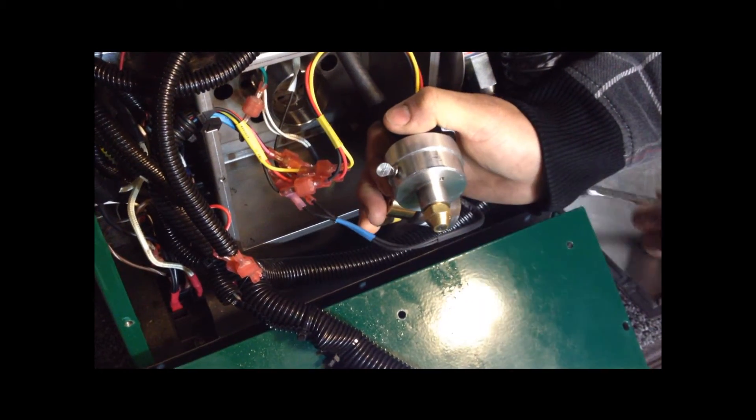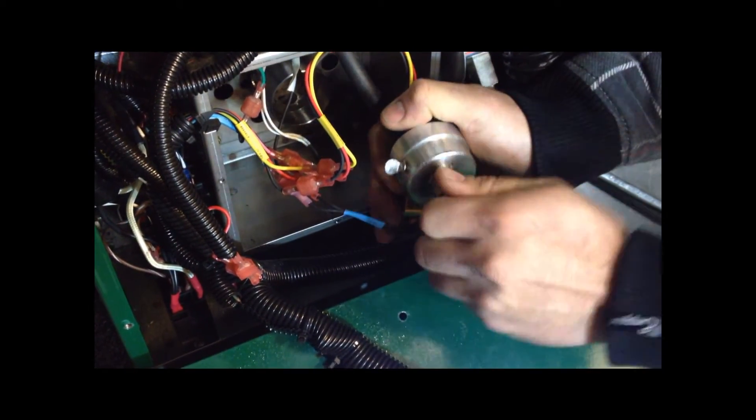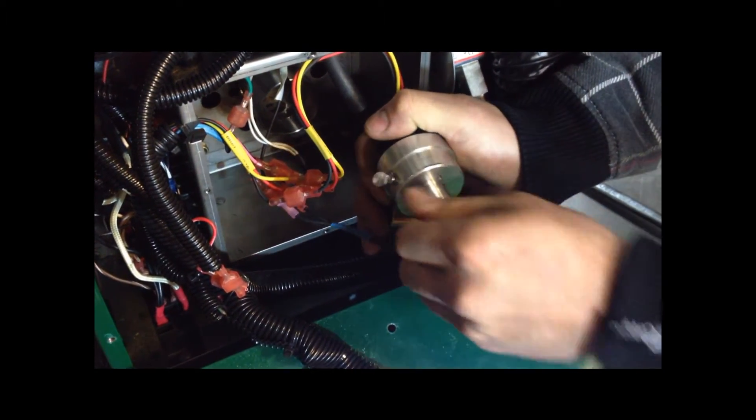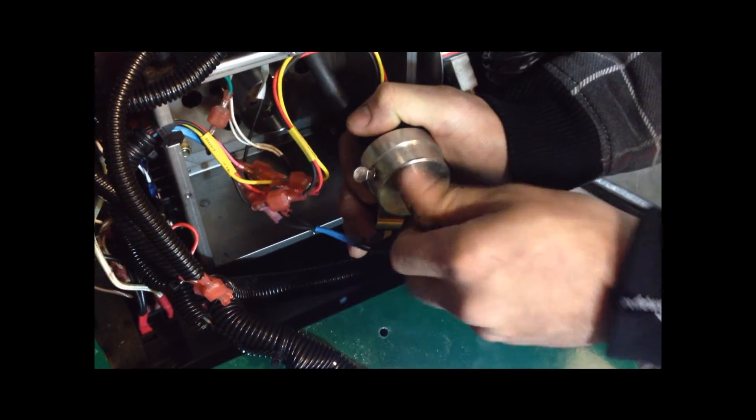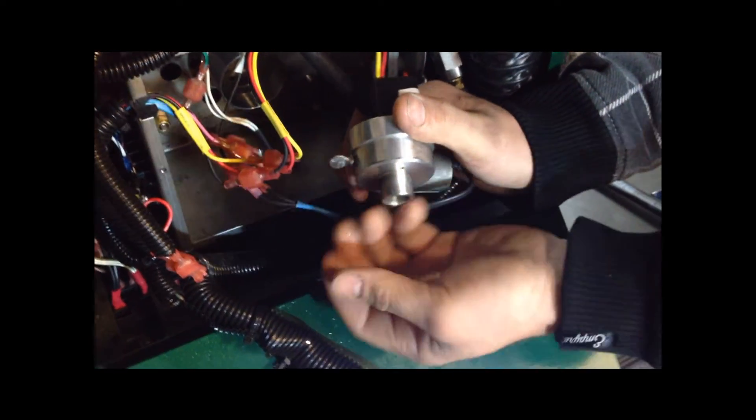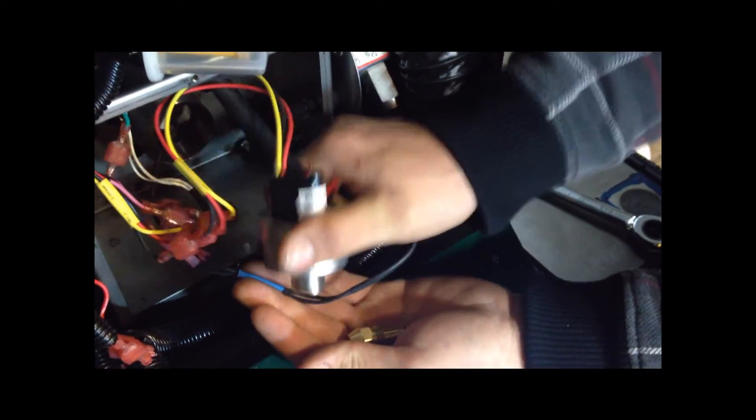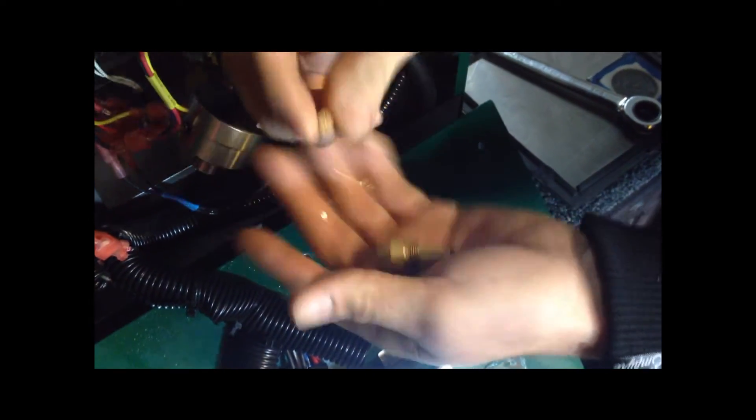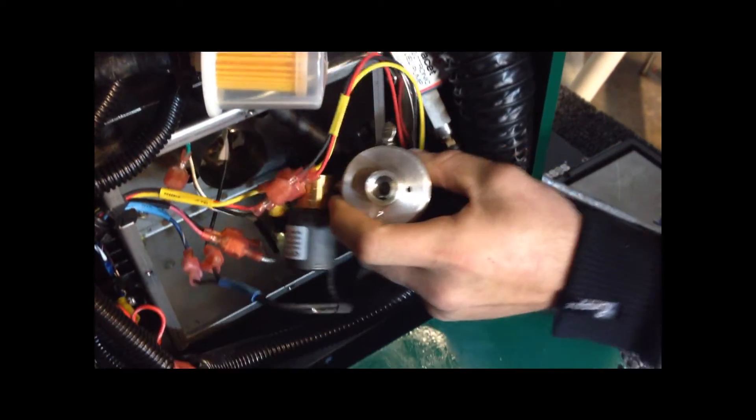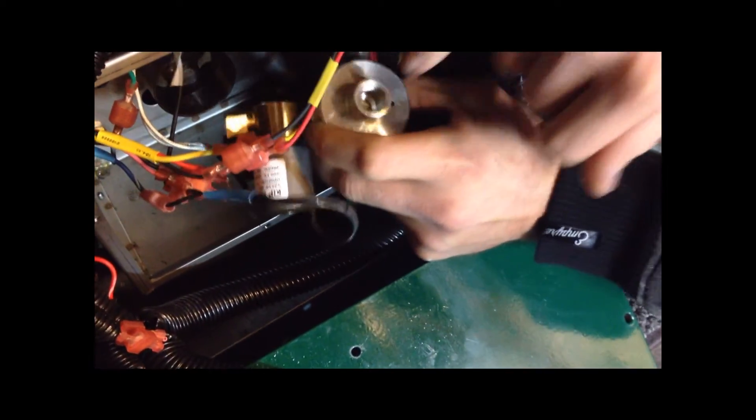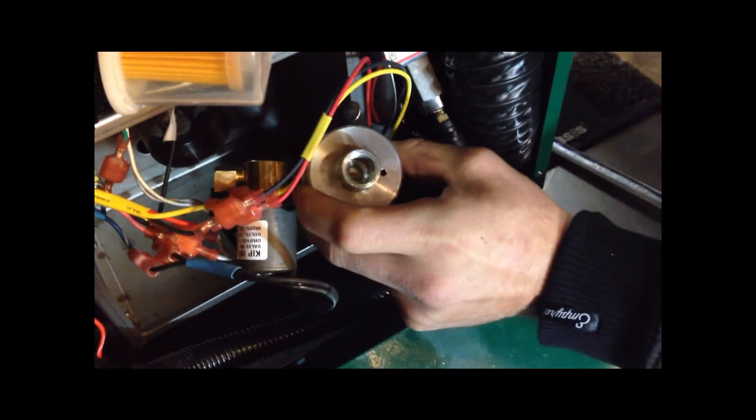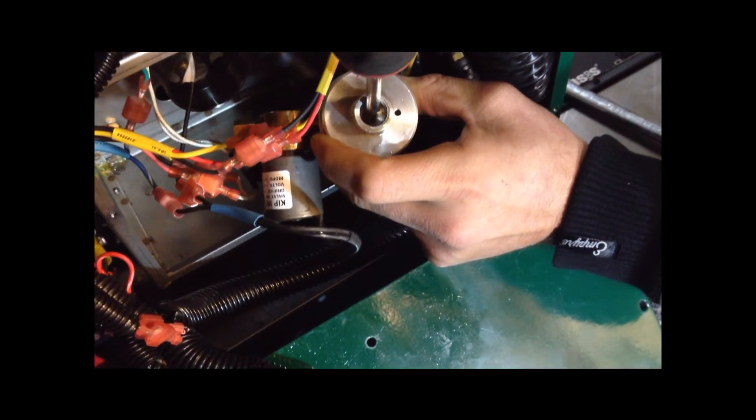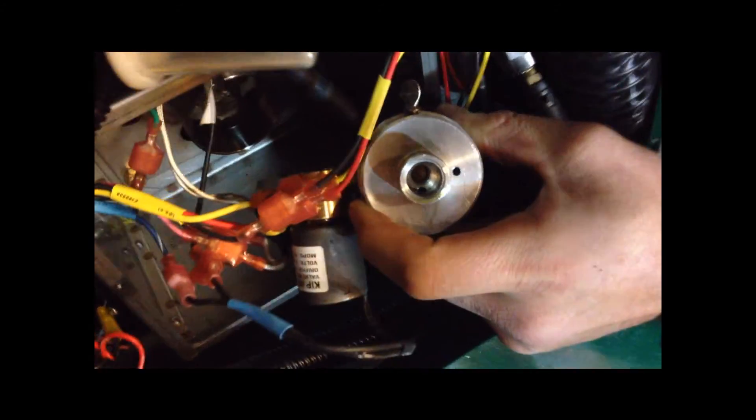And that's a 5/8ths wrench. Remove that nozzle, and there will be a stone filter behind it. You may need to tap it out to get that filter to drop out. There it is. Replace it. And when installing the new one, make sure that filter drops all the way down in there and seats itself.